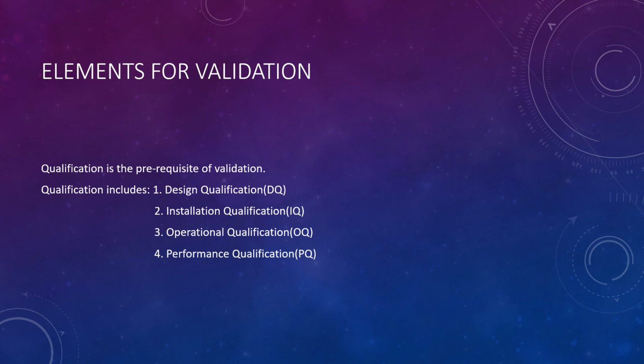The operational qualification. Here we check whether the equipment is performing to the criteria required during operation, and it helps in defining the upper and lower limits and the worst case limits of how the equipment is being operated.